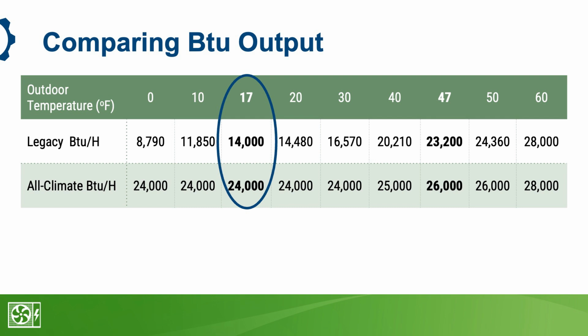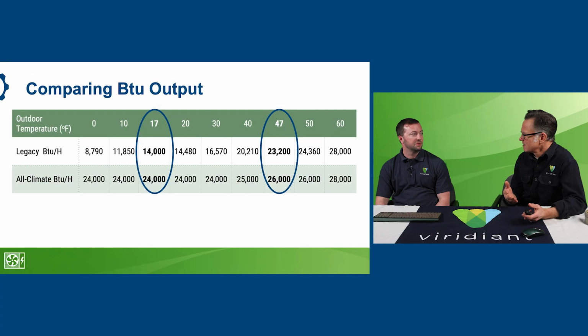And the heating performance of the home is shown in what we call design temperatures and what that piece of equipment will produce at design temperatures. 47 degrees is where we learn about the tonnage of the equipment. What's a ton? 12,000 BTU. So this equipment here is, we'd call it a 2-ton, either one of them. We've got the legacy heat pump on the top and the all-climate heat pump on the bottom. So when we look at that 47 degrees, we can see they're both around 24,000 BTUs, both around 2 tons.